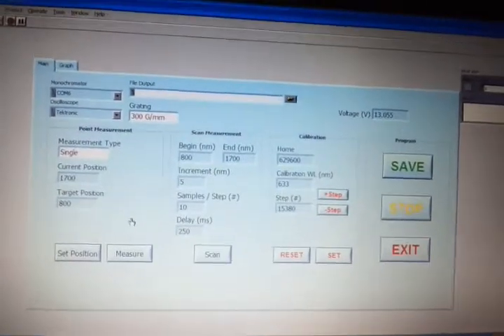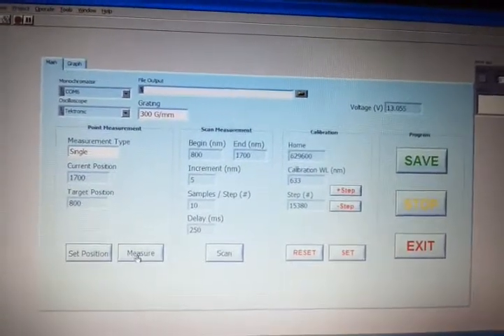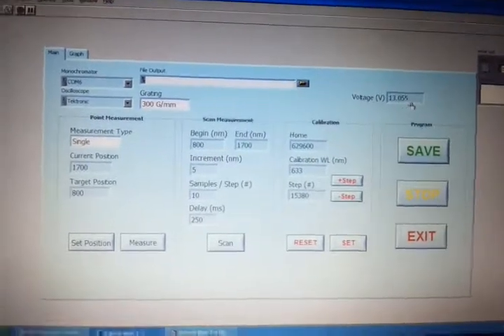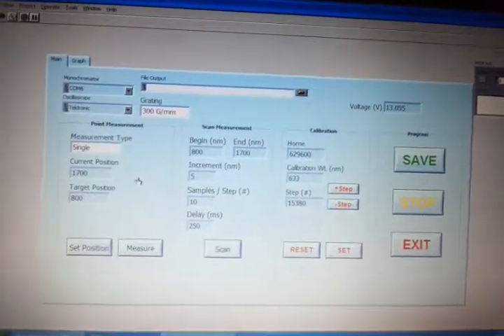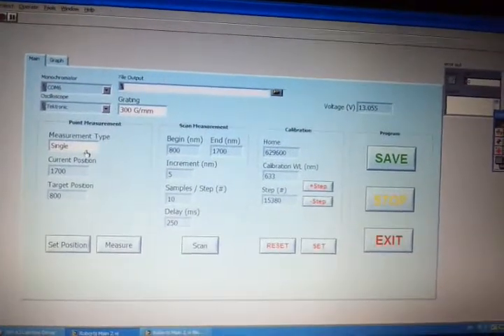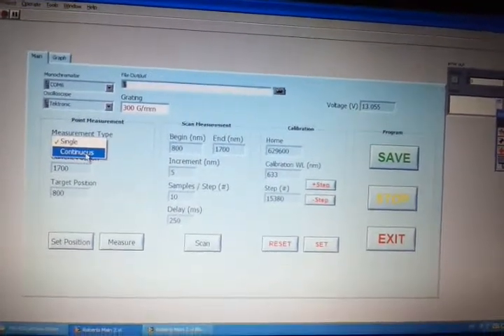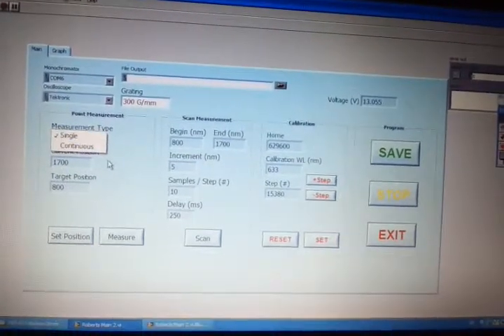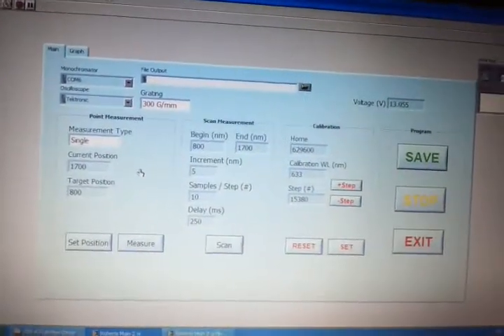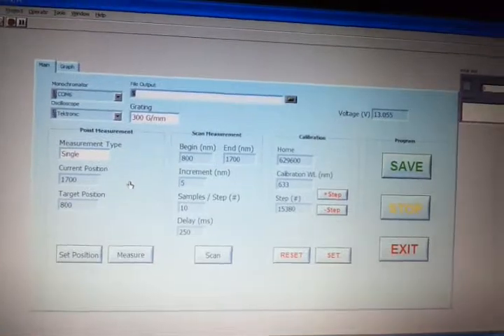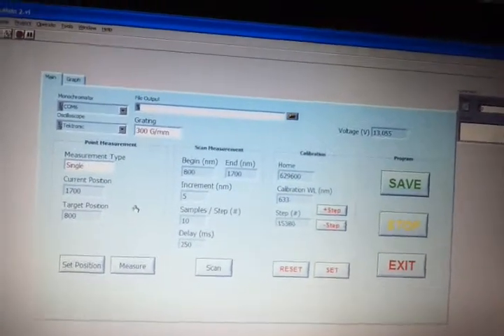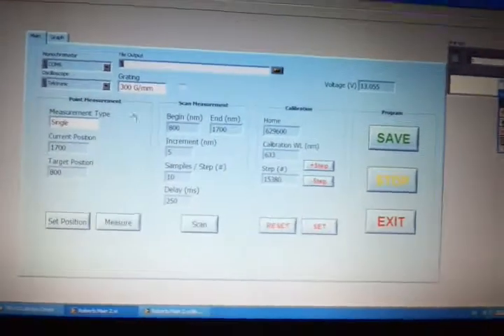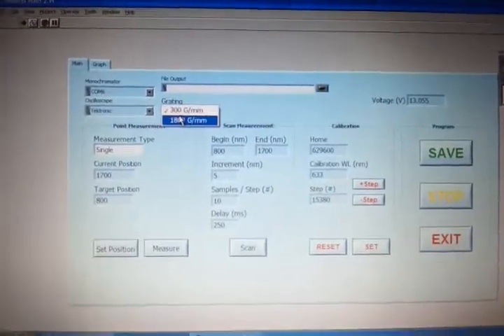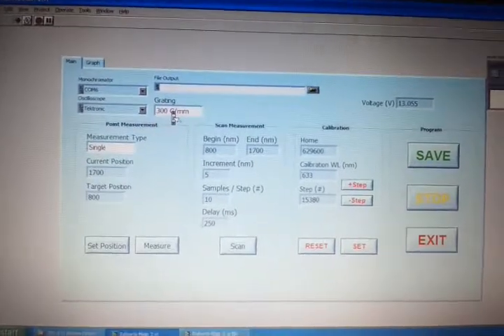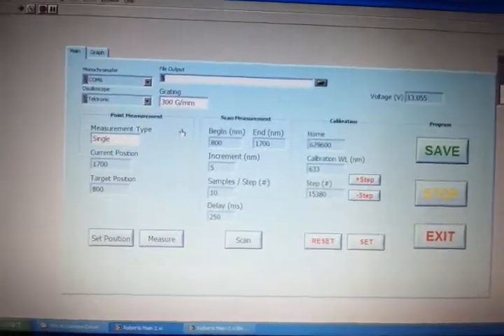If you want to record what the voltage output is, click measure. That will then tell you what this is, and you can write it down. You can decide whether you want to take a single or continuous measurement, and continuous will just keep outputting a voltage every second or so, whereas single just gives you 1 voltage output at a time. Make sure that you have the correct grating selected. Currently it's 300, but if you were to change that, make sure you do so there.